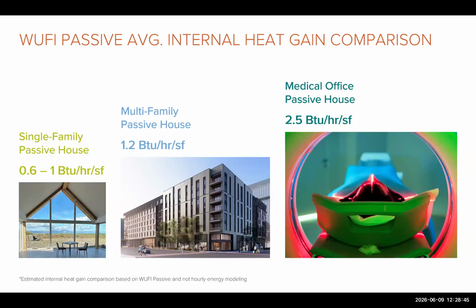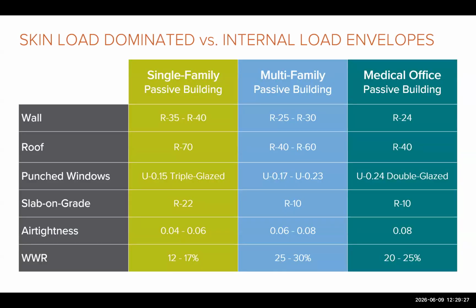As I mentioned earlier, these internal loads give off heat, which we refer to as internal heat gains. To quantify these loads, I'm going to compare three passive house projects in Massachusetts. So a single family has an internal heat gain of 0.6 to 1 BTUs per hour per square foot, whereas a multifamily is more condensed, has more people, more appliances, has a higher internal heat gain of 1.2. Whereas a medical office building is over double this with 2.5 BTUs per hour per square foot. This large increase is due to the medical and office equipment. So higher internal heat gains mean you can reduce envelope insulation without compromising performance because you have more people and more equipment to generate that heat.